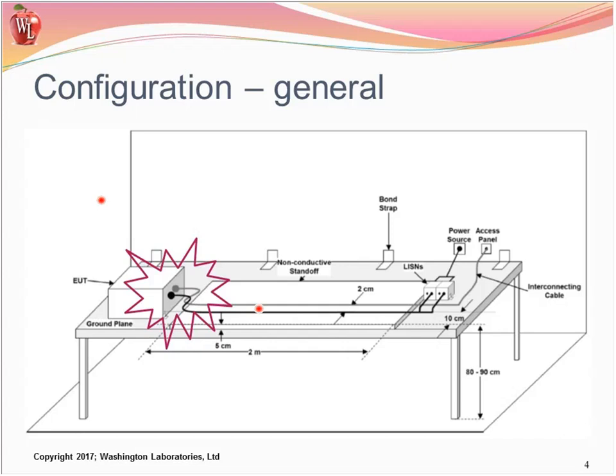We can see that the ground plane is present and the LISNs are connected. But this nice little ground strap I was referring to shows a very short, tight location, but with the requirement for the ground plane to be at least 30 centimeters from the back wall, that strap is going to be somewhat lengthy, and normally we have to have a place to connect it to the shielded enclosure wall. So paying attention to that little element says you need to use some very wide straps, or a 5-to-1 ratio, to minimize the inductive reactance for the RF. Even though the bonding may be good, the RF performance needs some good low inductance. And by the way, like normal, using multiple straps in parallel reduces the overall inductance, just like parallel resistors would.